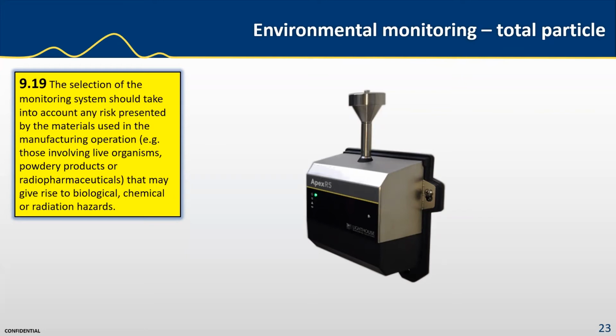E.g. those involving live organisms, powdery products, or radiopharmaceuticals that may give rise to biological, chemical, or radiation hazards. So again, the selection of the monitoring system is critical. The sensor type and design can impact here. I recommend you look for a sensor that has a sealed enclosure and all vacuum and communication cables are covered, like in this example. And this example shows a nice sloped top cover. And then also you can see that, or you can't see, there is no vacuum tubing exposed or communication cables.